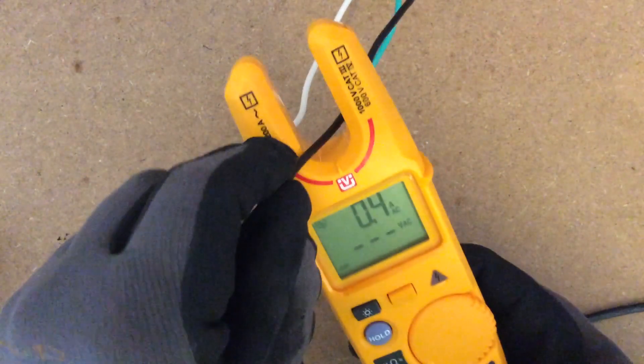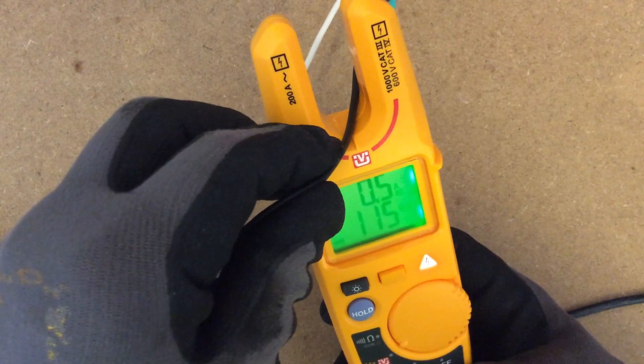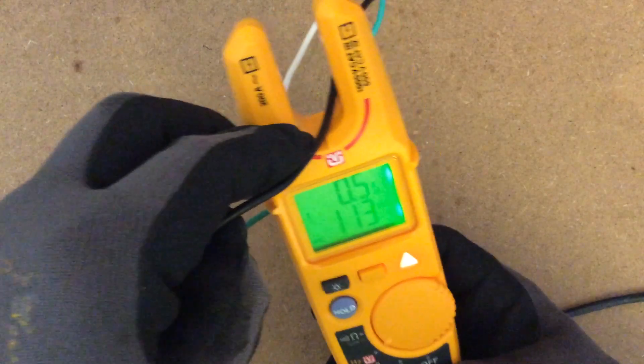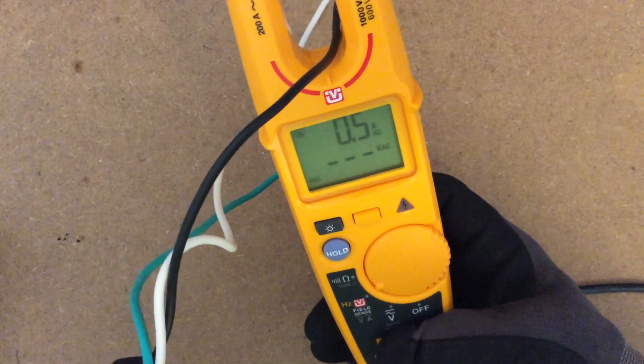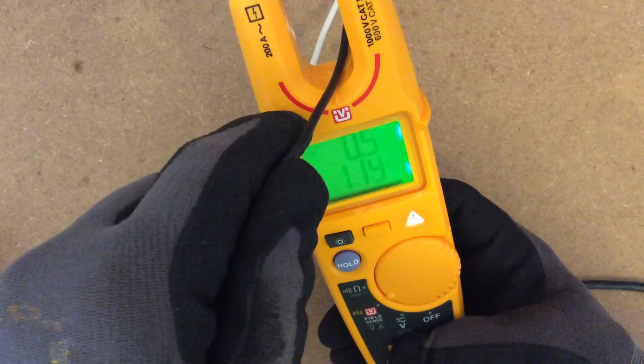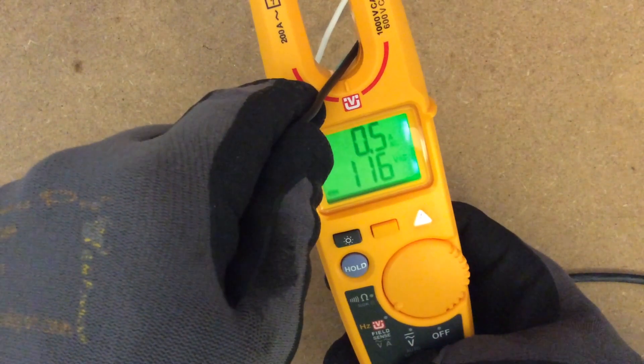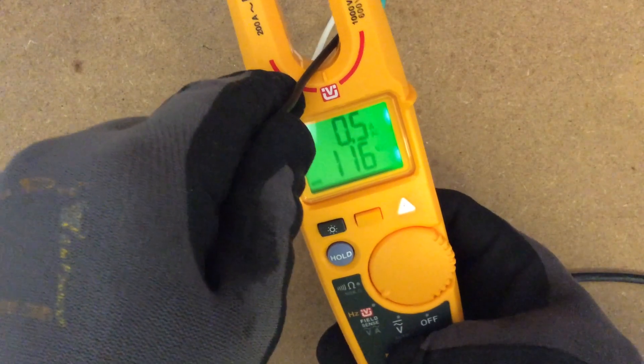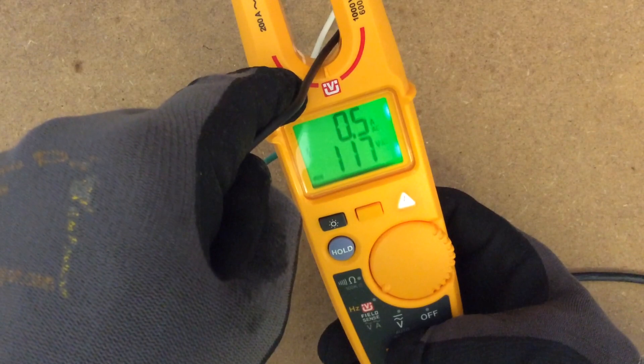For today's test we're using a box fan out in my shop. Look how fast that is — boom! It's reading 115 volts, 0.5 amps. Now, normally you wouldn't have to hold the wire — the wire I'm using is very flimsy, but in the refrigeration and HVAC electrical world the wiring is a lot sturdier. You'd just put the jaws up, press the wire against the dimple mark, and it starts reading. In this case we're reading 118 volts at 0.5 amps at the same time.